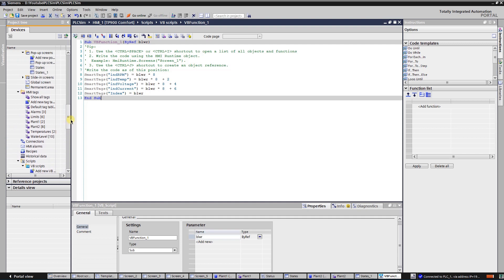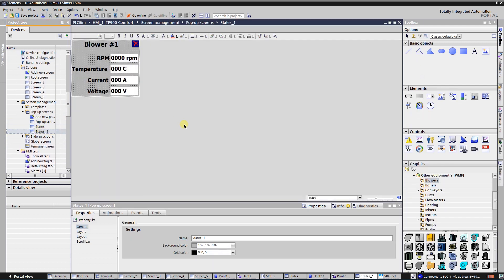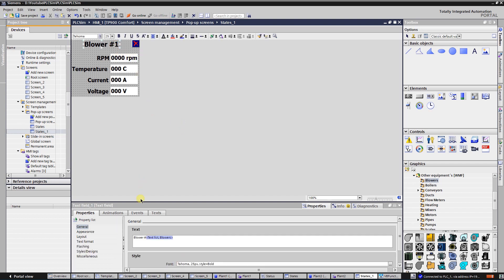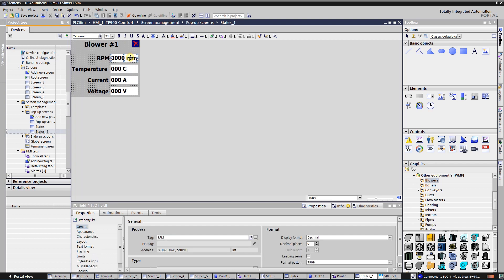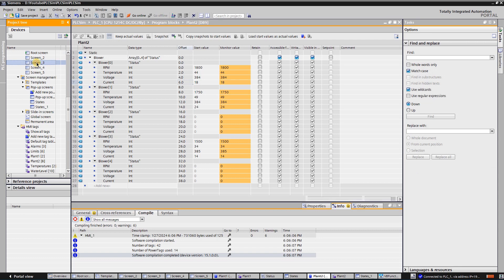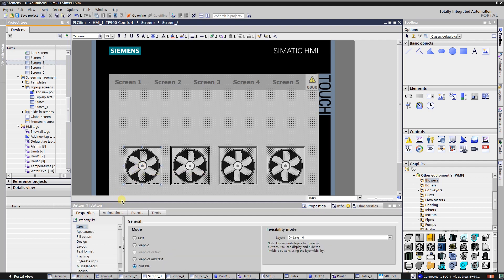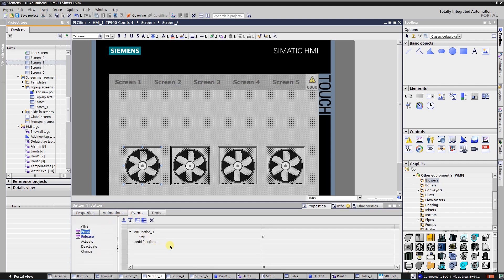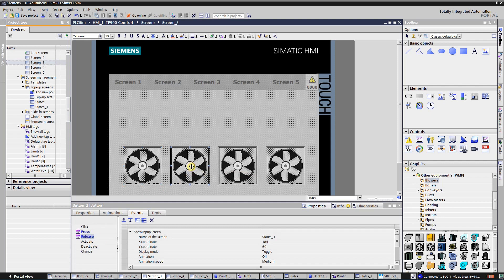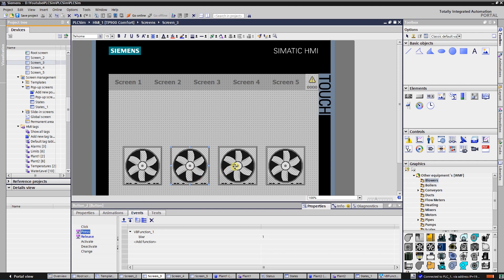Create another pop-up screen to show the values, and assign the corresponding multiplex tags for each output field. Create another screen with blowers. In the button events, on the button press event select the newly created VBScript. Set 0 for the first blower number. On release, call the corresponding pop-up screen. Repeat the same steps for other blowers by setting the correct blower number for the VBScript parameter.